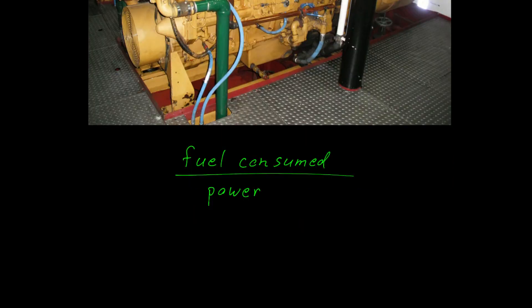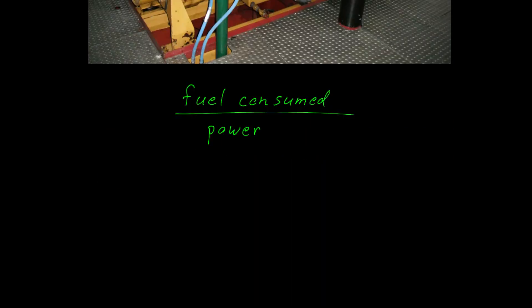As an example, let's consider a new Cat 3406, one that's rated at 400 kilowatts electrical. When it has 100% load on it, we can expect that it will consume 29.2 gallons per hour.